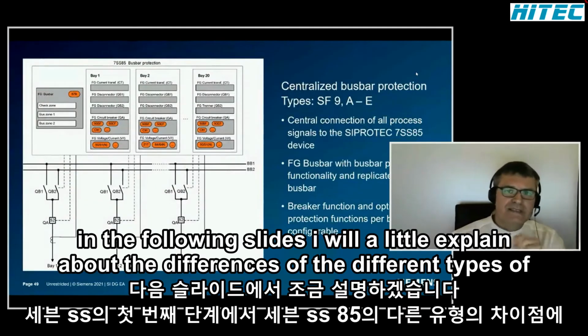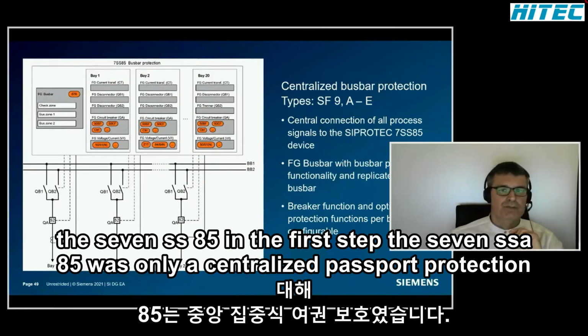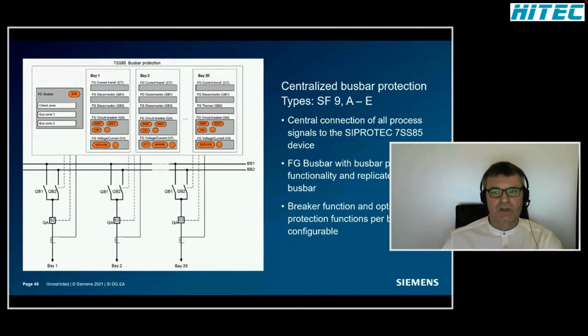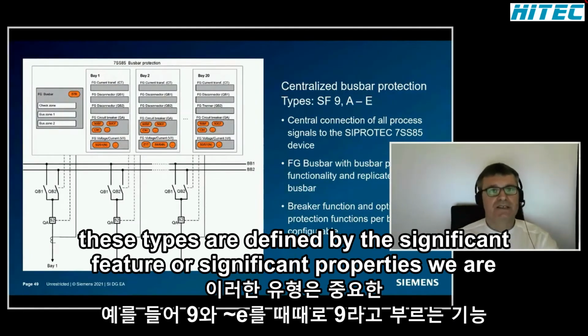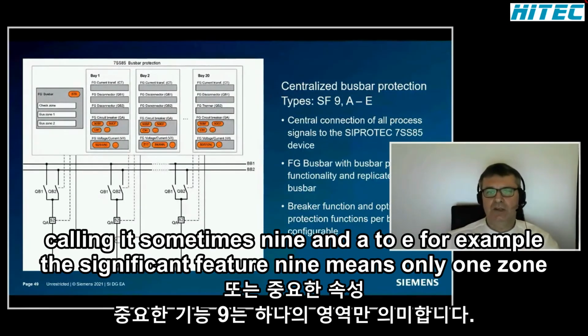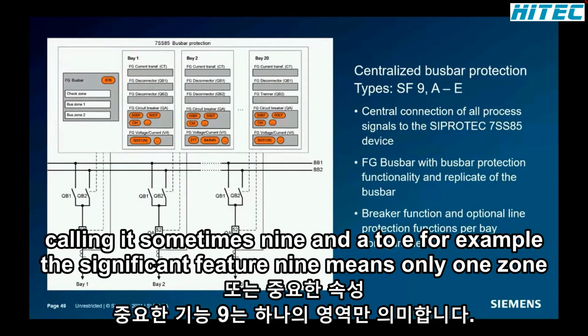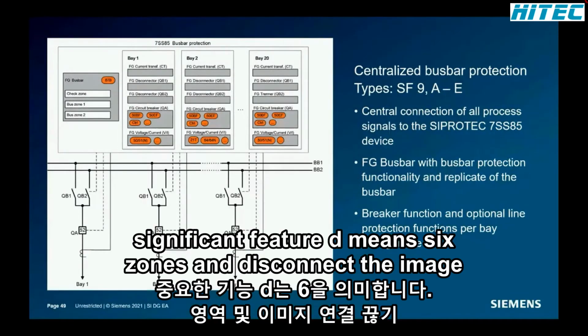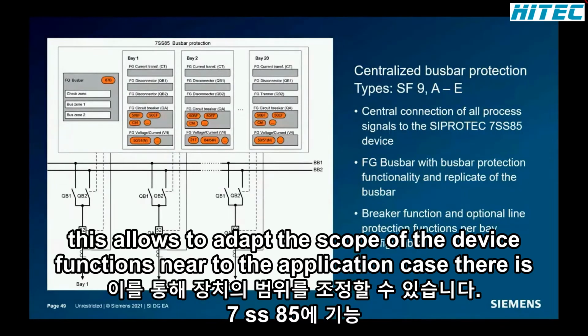In the following slides, I will explain a little about the differences of the different types of the 7SS85. In the first step, the 7SS85 was only a centralized busbar protection. These types are defined by the significant feature or significant properties, we sometimes call it 9 and A to E. For example, the significant feature 9 means only 1 zone. Significant feature D means 6 zones and disconnector image. This allows to adapt the scope of the device functions near to the application case.